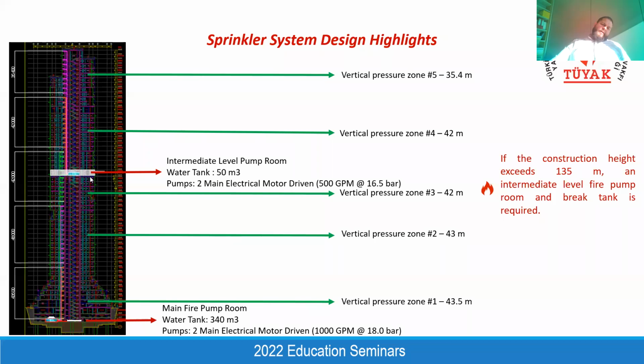And also this is a very important design criterion for the architects regarding the mechanical requirements. As per Turkish fire codes, we need to have separate vertical pressure zones for the water-based suppression system because we have some limitations, both minimum and maximum, for the system pressure. For example, at the highest point, we need to have at least 4 bar of water pressure. And also at the lowest point of this vertical pressure zone, the maximum pressure is limited to 12 bars. That's why for each 45 meters, we need to have a separate vertical pressure zone. It is also the same for the daily usage systems. For example, the heating and cooling system also has some vertical pressure zoning. But today I'm just explaining from the fire point of view.